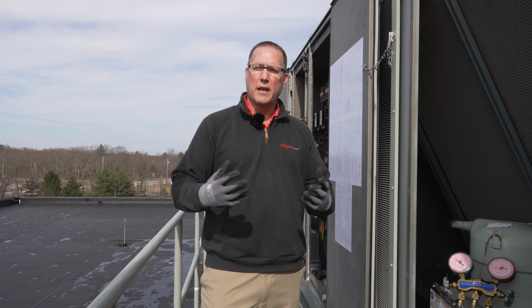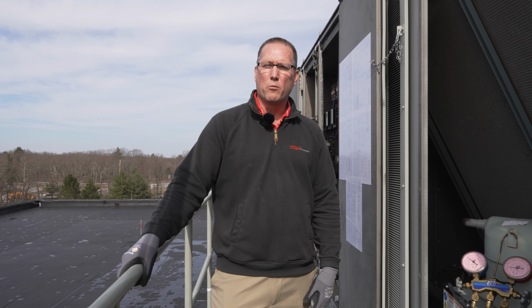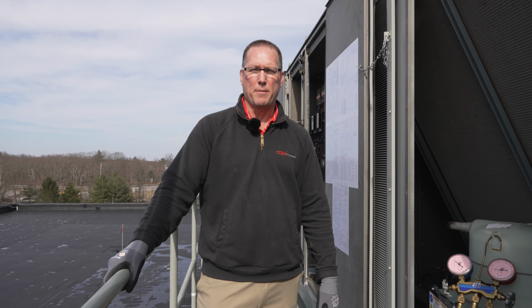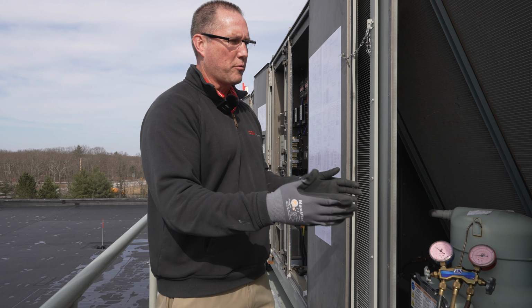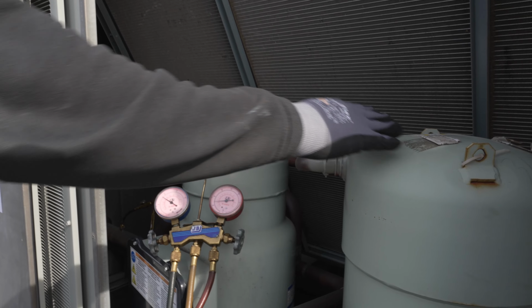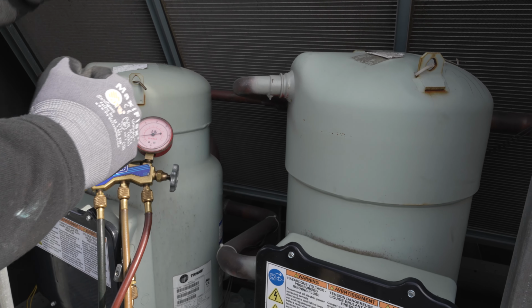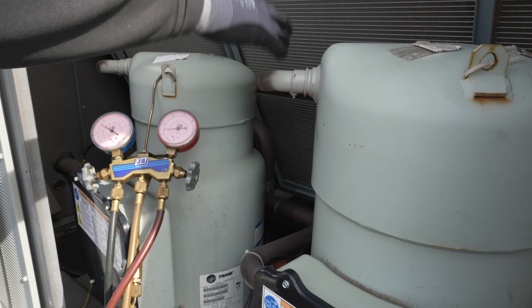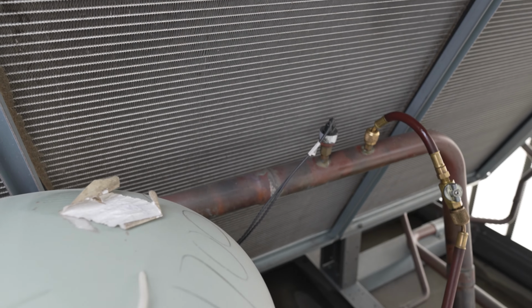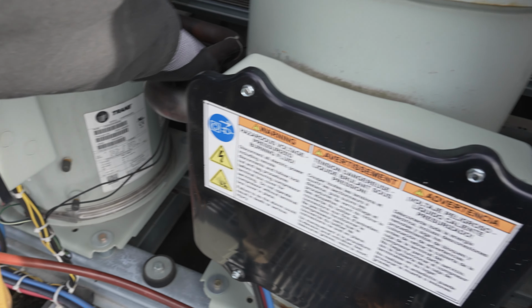We wanted to put together a short video to show our clientele exactly what we do when we're up on the roof doing maintenance on your equipment. So we're going to start here with the compressor section. The compressor is kind of like the human heart. It's a pump. It pumps refrigerant out to the system through the piping, and then it brings back the refrigerant on the suction side of this pump. So no different than the heart.